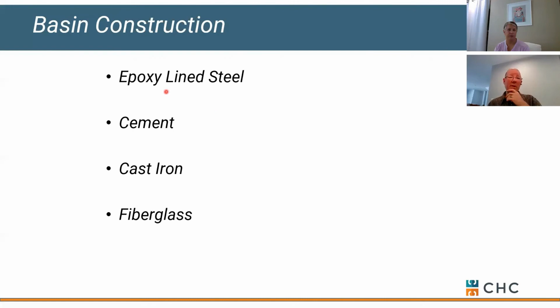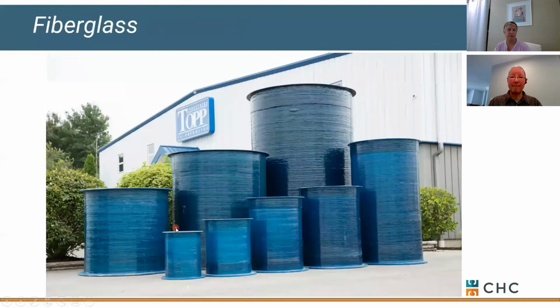We could use a simple steel, but it's normally epoxy lined. You can also look at a utility vault as a cement basin. You can go cast iron if you like. Fiberglass is another option. Typically, when there's a pour on a new site, they're just going to pour the basin as part of their concrete pad setup. If you're doing a retrofit, you might be looking at a fiberglass basin as a drop-in. That's certainly an option for you. One of the issues with fiberglass basins is it's a lot of empty air on the back of a truck. Freight rates can be pretty high here. They take up a lot of volume, but there's not a lot of weight to them. So that can be a challenge based on freight.